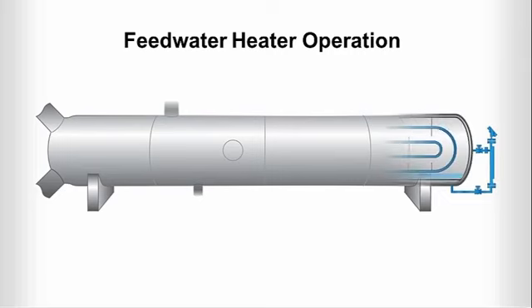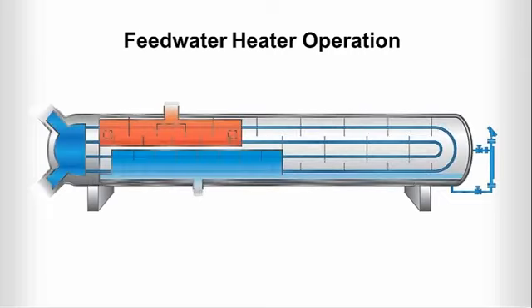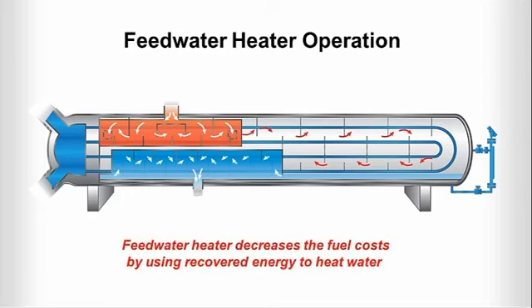Feed water heaters use the heat of condensation to preheat water to the correct temperature for the boiler. During this process, shell and tube heat exchangers allow feed water to pass through the tube side and extract steam from the turbine to the shell side. The primary benefit of this process is that the feed water heater decreases the fuel costs by using recovered energy, rather than costly hot gas, to heat the water.